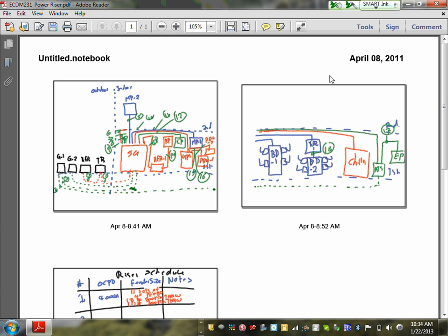What happened in the past is that the generators, when they pick up a 4,000 amp switch here, cannot sync together online within 10 seconds and pick up the emergency load. That's why they forced you to put that one in. That has always been a debate, a waste. It is a waste. So the automatic transfer switch really works only for probably 15 seconds, maybe a minute maximum, and then it goes back to the switchgear.